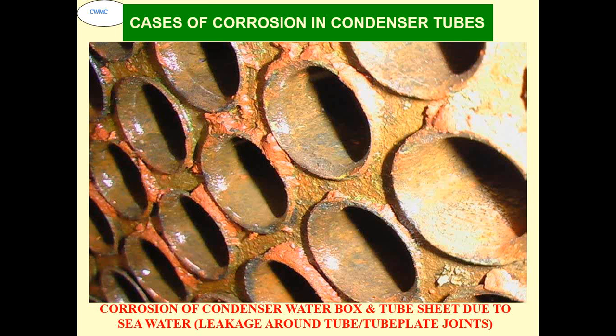A typical problem that you see is severe crevice corrosion as well as dissimilar metal welding galvanic corrosion at the tube plate of your heat exchanger. That is the most prone area, where the tubes are expanded and small crevices are formed in which the water goes, and a differential cell is created in terms of either differential oxygen or differential concentration of chemicals, and you get crevice corrosion there. Or because of the different tube sheet material and tube material, you can have galvanic corrosion and severe corrosion there. Third, in that area you can have a concentration of microbiological fouling, and microbiologically induced corrosion can take place all around that area, depending upon the metallurgy that we are talking about.